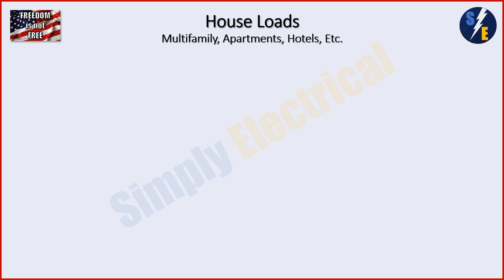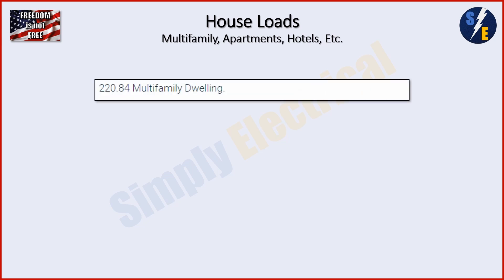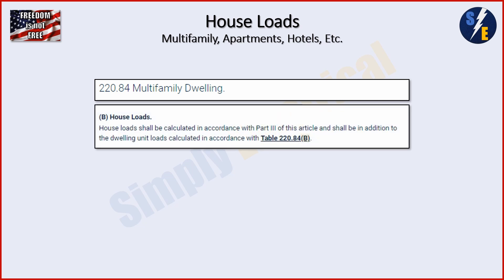First we're going to talk about what house loads are, then we're going to go to the code to see where they're used and how we put them into our calculations. The only place in the NEC that even mentions house loads is 220.84 under multifamily dwelling, because that is mainly where you're going to see these. Because of that, we're going to go to 220.84B. It says: house loads shall be calculated in accordance with part three of this article, and shall be in addition to the dwelling unit loads calculated in accordance with table 220.84B.